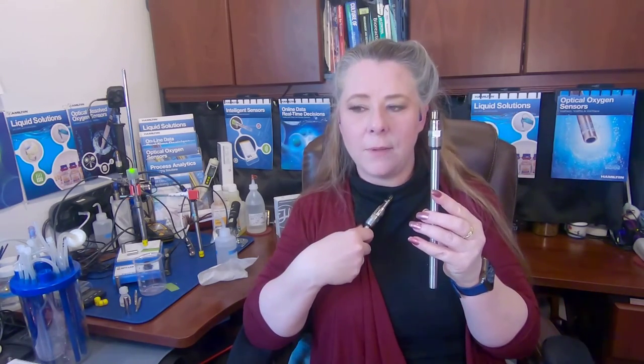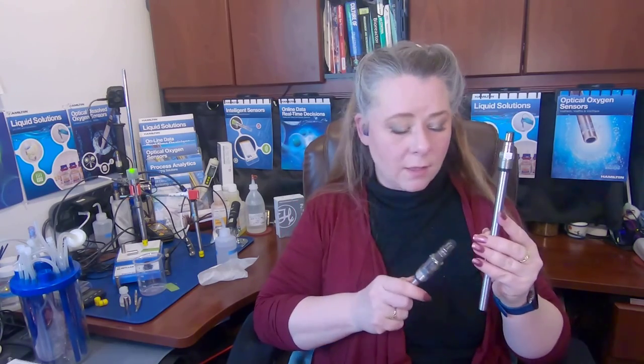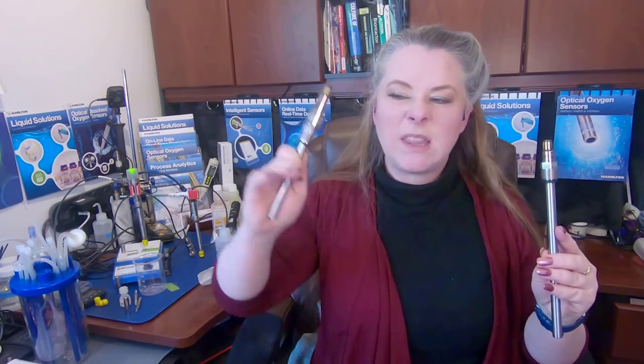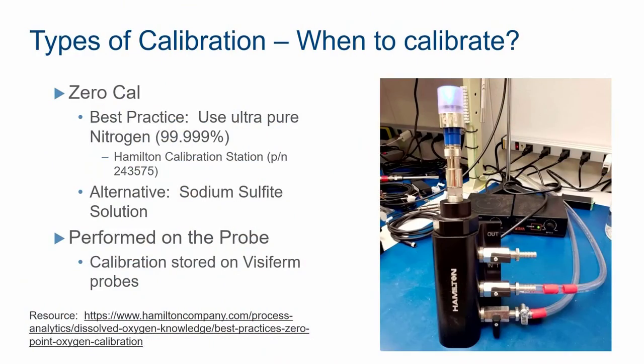Analog sensors do not have the ability to hold calibration, so we can never calibrate the sensor itself accurately. What we can do is calibrate it, get some numbers, and then manually input that into the bioreactor. But mostly what we do is bypass it, calibrate to the bioreactor, and ignore that the probe ever has calibration. So you pretty much always have some amount of error in your measurements with polarographic measurements because you can't really compensate for it that well. Okay, first we're going to talk about how to calibrate the sensor itself, and then how to calibrate in a bioreactor, because these are the two steps that you will run into in the real world.